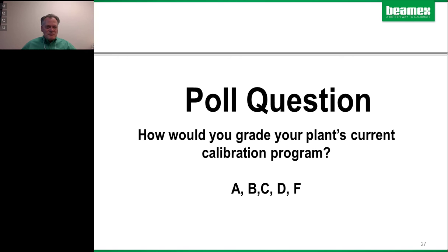All right, so I think it's time to move on. We're going to do the demo next. Ned, thank you so much. And this demo is actually pre-recorded, but I did this two days ago, and it was 24 minutes. We condensed it down to 11, and everything that happened is real. If you have an interest in seeing everything that occurred, then I think we can probably make a link for that. But the key thing is that we're doing an as found, and then we do an adjustment through the communicator where I do a trim, and that part is completely skipped. I wanted to fast forward through it, but we weren't able to do that. And then the as left is done. But just know that there was a trim that actually occurred in the middle. And here we go.